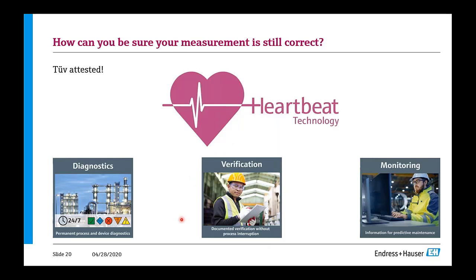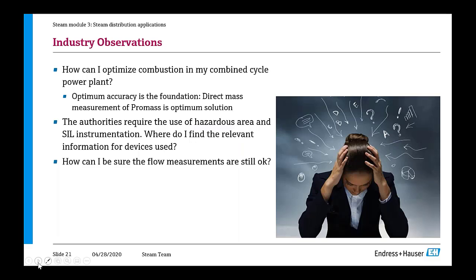Then you can do verification. So this is important if you want to prove to the authorities, yeah, we believe this measurement is still okay. And this is typically if you have measurements that have an influence onto the environment, like natural gas measurements. And last but not least, monitoring can help you to do some predictive maintenance, to get some information out of these devices. So Heartbeat also, as I mentioned before, for the thermal mass, for instance, enables you to detect if there's moisture present, or if the device is drifting because of coating on these sensor probes.